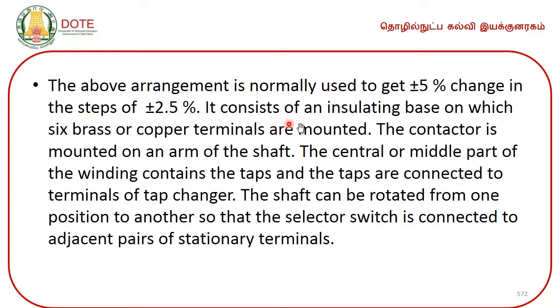It consists of an insulating base on which 6 brass or copper terminals are mounted. The contactor is mounted on an arm of the shaft. The central or middle part of the winding contains the taps, and the taps are connected to terminals of the tap changer. The shaft can be rotated from one position to another so that the selector switch is connected to adjacent pairs of stationary terminals.